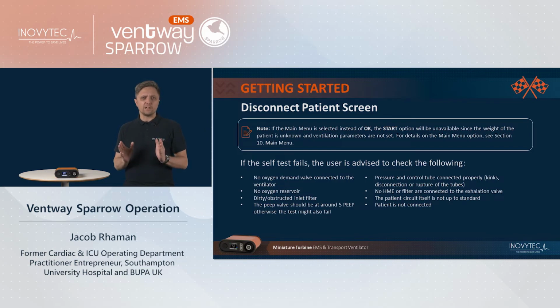If the self-test fails, the user is advised to check the following. Check the oxygen demand valve is disconnected from the ventilator. Check that there is no oxygen reservoir connected. Check for a dirty or obstructive inlet filter.